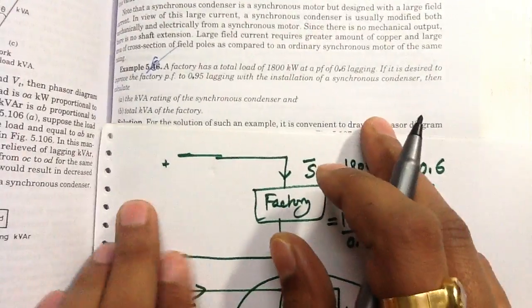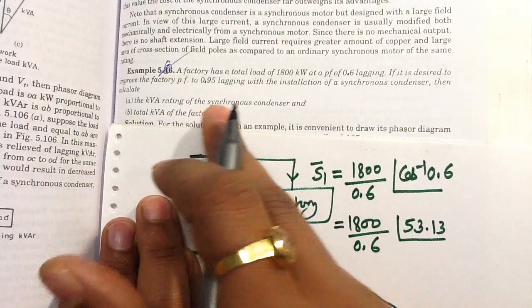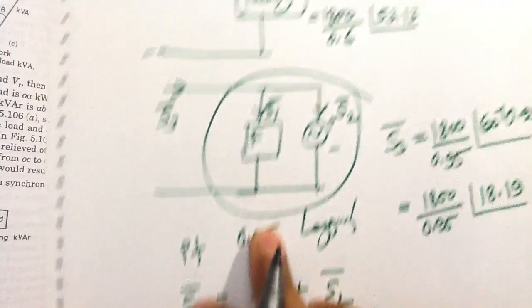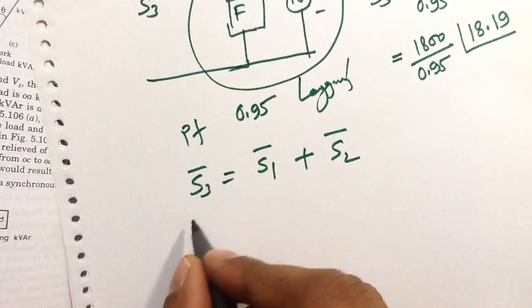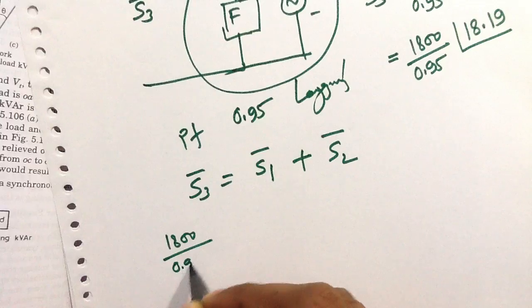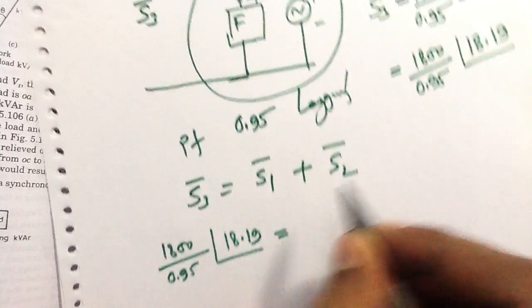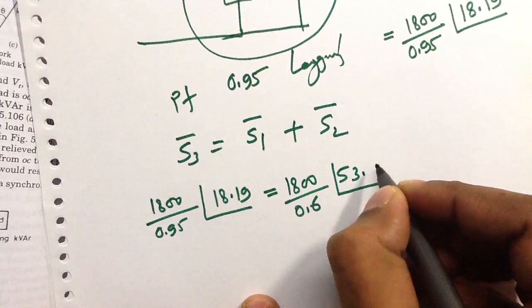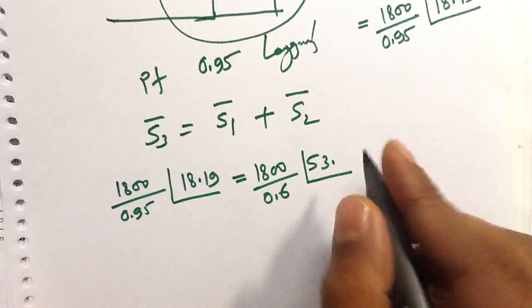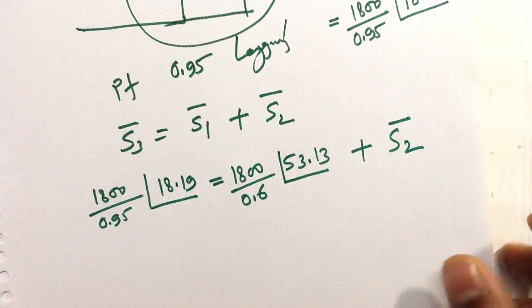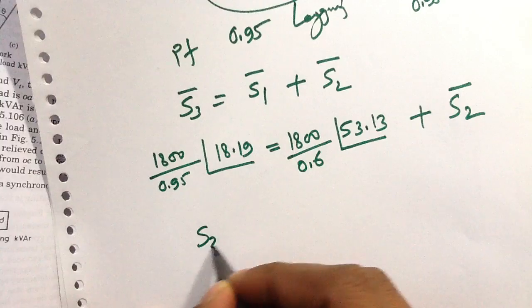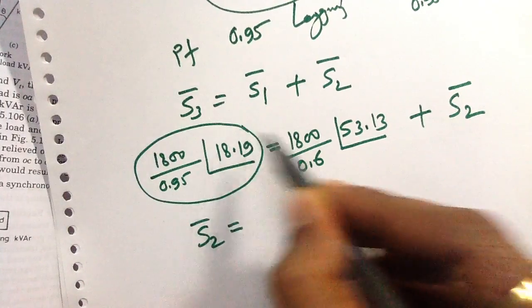We have to calculate the KVA rating of the synchronous condenser used. Substituting the values of S3 and S1 into the equation: S3 equals 1,800 divided by 0.95 at angle 18.19 degrees, and S1 equals 1,800 upon 0.6 at angle 53.13 degrees, plus S2. To find the KVA rating of the synchronous condenser, we calculate S2 equals S3 minus S1.